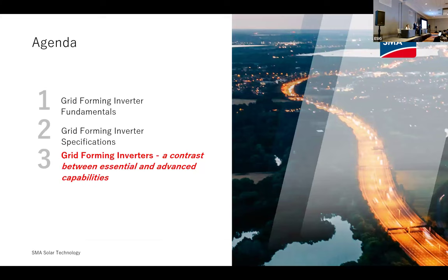Now I want to talk about a question asked in the earlier session: can we just turn this on? What's the difference between grid forming and grid following — can we just flip a bit and change this into a grid forming inverter? The answer is, it depends, as most answers are in this engineering environment. But understanding where these capabilities come from is really important. For an existing SMA inverter, we can turn it on in software, so to speak, but you won't get the same benefits to the network as you would if you designed a plant from the very beginning with those stability services in mind.